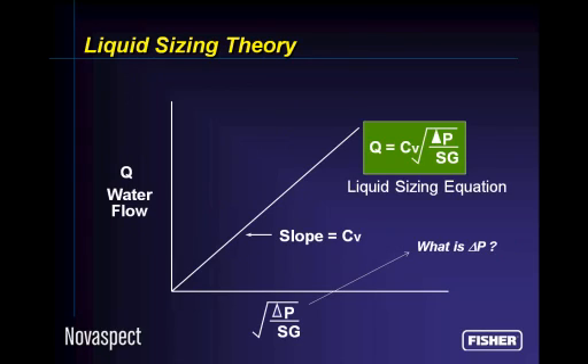All right, let's talk about liquid sizing theory a little further. The equation for sizing a valve is in this green box. The Q in gallons per minute equals the CV times the square root of the differential pressure across the valve divided by the specific gravity of the fluid. The differential pressure, again, is the difference in pressure between the pressure at the inlet of the valve and the pressure at the outlet of the valve.